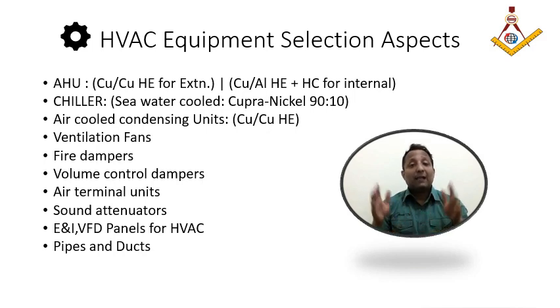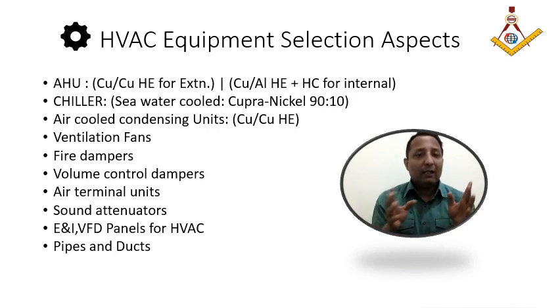So water cooled is given the first option, but in case the water cooled facility is not available, say for standalone platforms without accommodation, consisting only of an electrical room, there's no water provision since no water is required. In that case, the last option is the air cooled system. They go for a large capacity air cooled chiller, or mostly an air cooled condensing unit with an AHU arrangement.